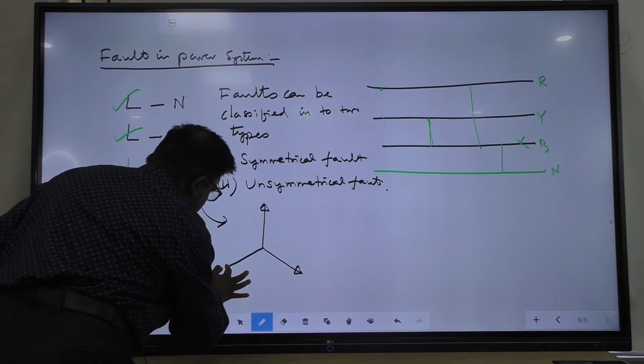When the magnitude of the three currents are equal - this is IR, this is IY, this is IB - IR equals IY equals IB, magnitude equal, and angle between them is 120 degrees, we call this a symmetrical fault current. Clear or not, any doubt? If the magnitude of the fault current is equal in all three phases and the angle between the three phases is equal to 120 degrees, we call this a symmetrical fault current.